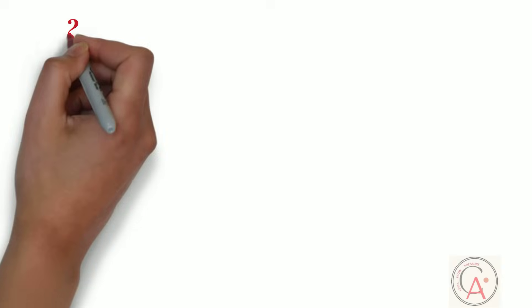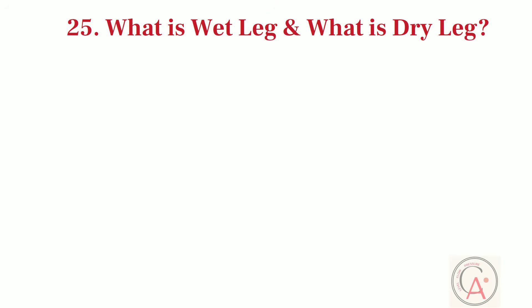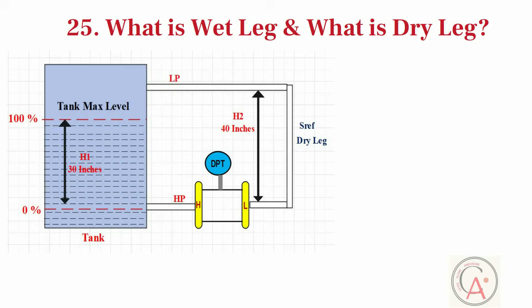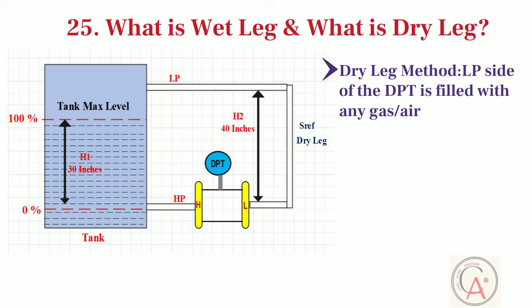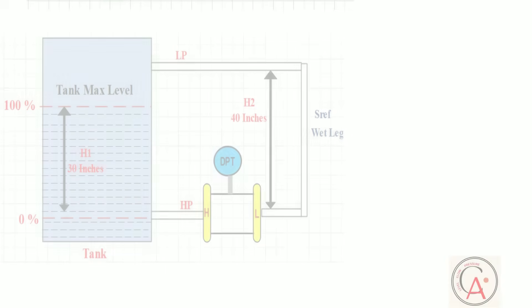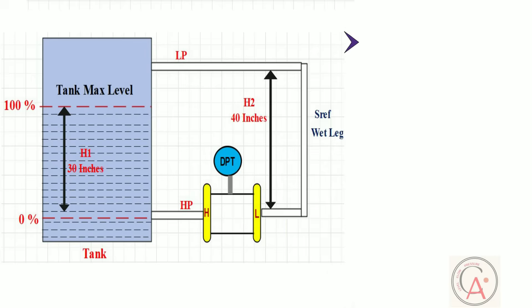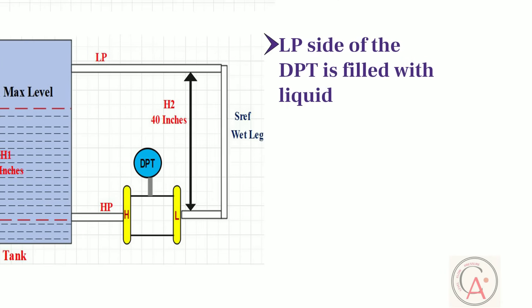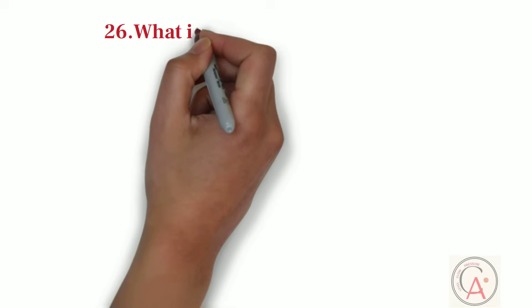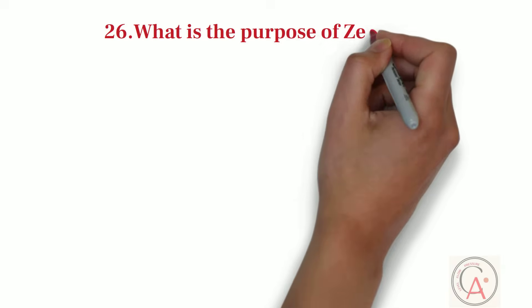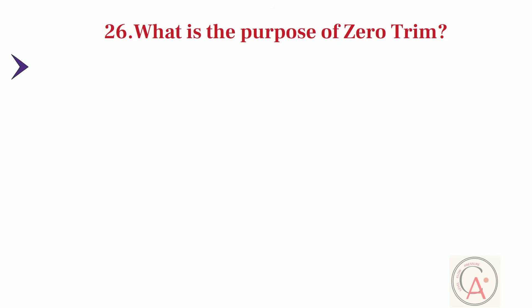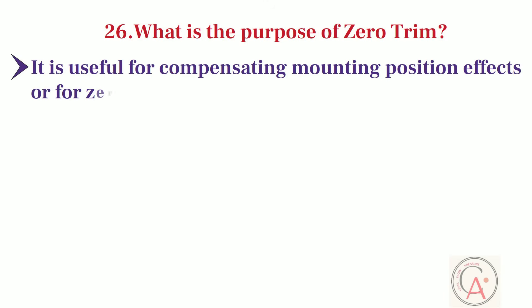Twenty-fifth question is, what is wet leg and what is dry leg in level measurement? In dry leg method of calibration, low-pressure side of DPT is filled with any gas or air. And in wet leg method of calibration, low-pressure side of DPT is filled with any liquid. Next question is, what is the purpose of zero trim in pressure transmitter and in differential pressure transmitter? Zero trim is useful for compensating mounting position effects, or for zero shifts due to static pressure in differential pressure applications.